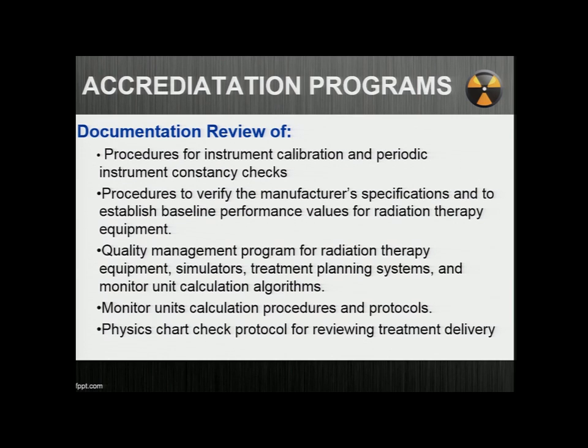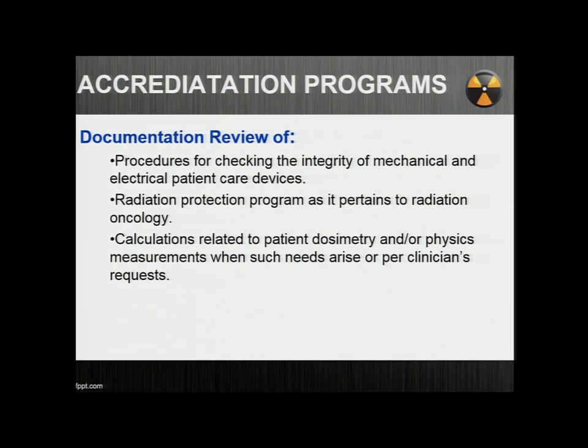And also, procedure: physics chart check protocol for reviewing treatment delivery. In other words, they will have a protocol in place for how they do chart checks and what they're expected to check off. So there's checklist galore in these departments. They'll also review checking the integrity of mechanical and electrical patient care devices. I think of this along the lines of what the accreditation programs want to know you have a policy for. I think of HDR units. I think of a source coming out or not coming out, or a source coming out and not going back in. I think of all of the integrity of these devices, and are they doing the testing that the manufacturer said, you need to make sure you're looking at this and testing it with this frequency? Are they doing that? For the radiation protection program as it pertains to radiation oncology, how do they train their staff every year?